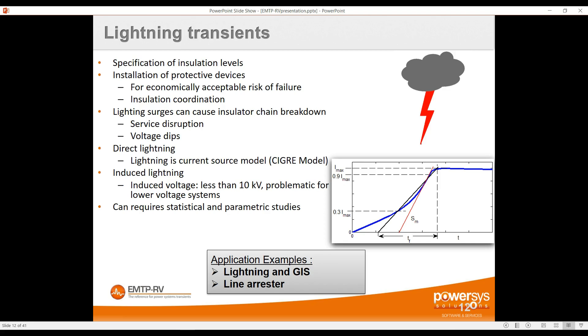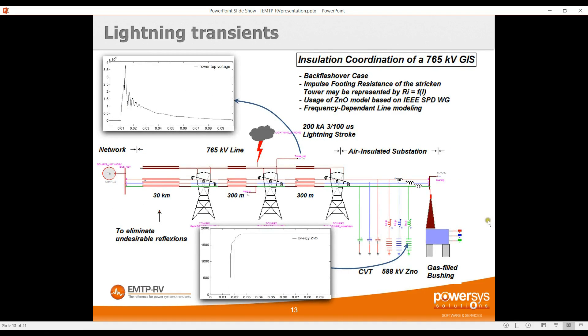Lightning transient is a very typical application case and part of insulation coordination. In EMTP we have the Cigré lightning model — a current source in parallel with a resistance, where the current source has a specific shape respecting the Cigré model. You connect this current source wherever you want on the network. Lightning studies are very local, requiring careful modeling of the substation in detail: all conductors, buses, stray capacitances of equipment, each span of the line, and so on. For the rest, you can use a network equivalent.